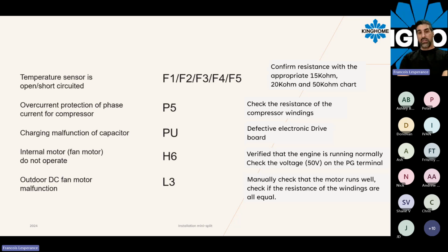If you have a bad compressor, because the resistances between each winding are not equal, for example, then under the Kinghome warranty you will get a new unit. We will not stock compressors. We will not have you change any kind of compressor or condenser if a major leak is happening, but we will do a unit exchange right away. The thing is, we just want to make sure that you have checked whether it's the board that is defective. If it's a PU error code, now it's related to the capacitor on the drive board. So basically, we will have to change the board.